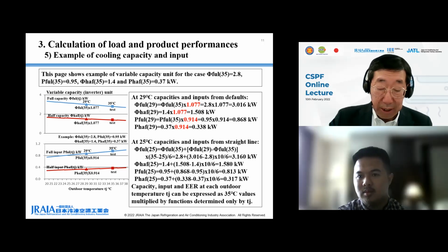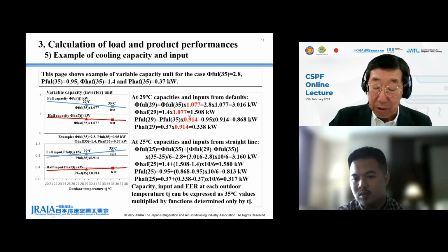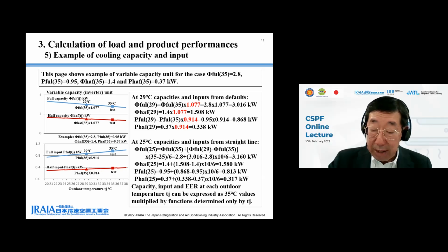29 degrees C half capacity is 35 degrees C half capacity 1.4 kilowatt multiplied by 1.077 equal to 1.508 kilowatt. 29 degrees C full input is 35 degrees C full input 0.95 kilowatt multiplied by default 0.914 equal to 0.868 kilowatt, and 29 degrees C half input is 35 degrees C half input 0.37 kilowatt multiplied by 0.914 equals 0.338 kilowatt.